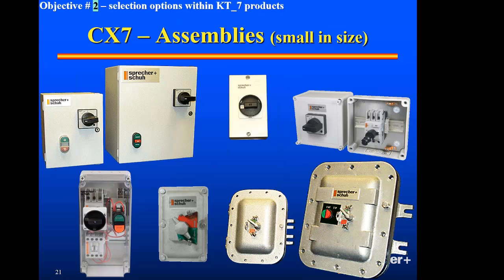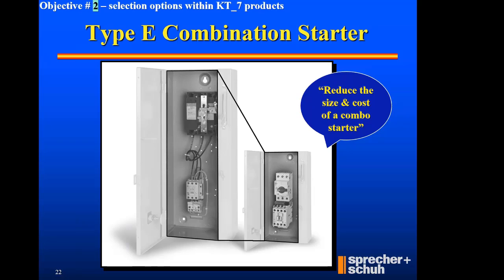Sprecher and Schuh offers catalog page offerings for enclosed components of KT7 enclosed, or if I add a contactor, now I'm calling it a CX7. So we can enclose these kinds of products in whatever integrity type requirement is needed for the atmosphere. We've got IP rated plastic inexpensive enclosures. We've got metal enclosures. We've got fiberglass 4X enclosures. We've got type 7-9 explosion proof enclosures. So given the circumstance and the requirement, absolutely, we could house that assembly.